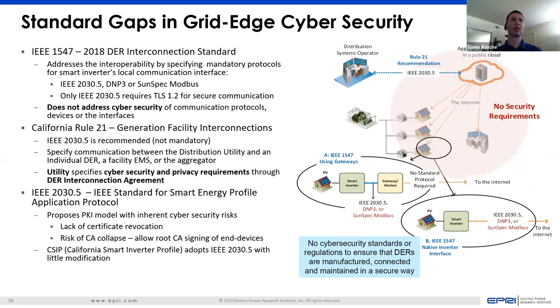In addition, when you look at some specific grid edge systems, there are standards gaps in this space. I've highlighted three different standards and rules related to DER and grid edge systems. One is 1547, a DER interconnection standard, which focuses on interoperability and specifies some mandatory protocols that need to be supported at a smart inverter's local communication interface, specifying it should use IEEE 2030.5, DNP3, or SunSpec Modbus.